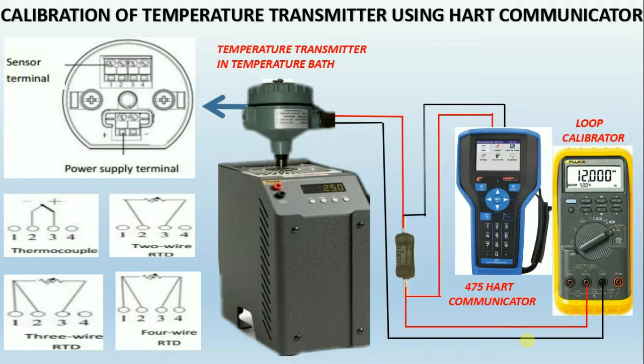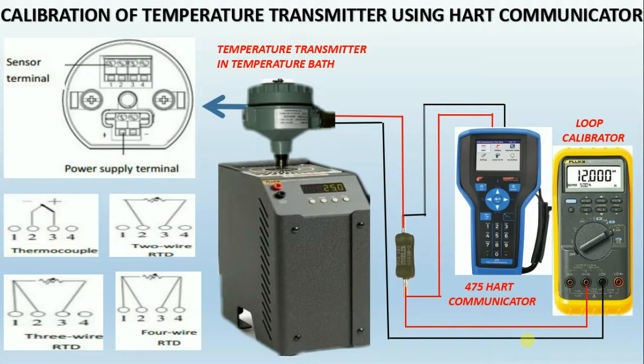After completing the connection, set the zero temperature value in the calibration bath according to the lower range value in HART, and check the corresponding 4 milliamps in the loop calibrator. If it is not showing the corresponding milliamps, then using HART, perform the lower sensor trim.